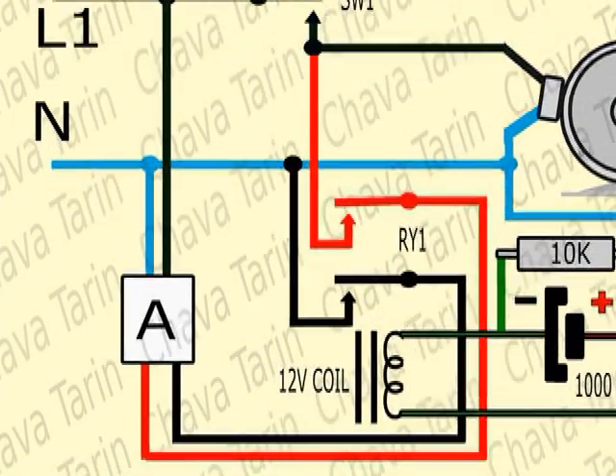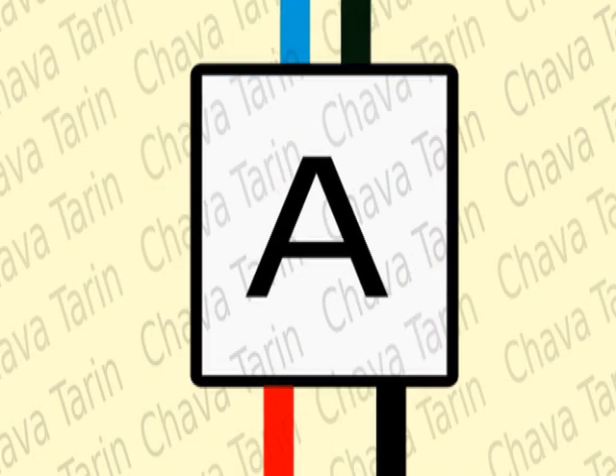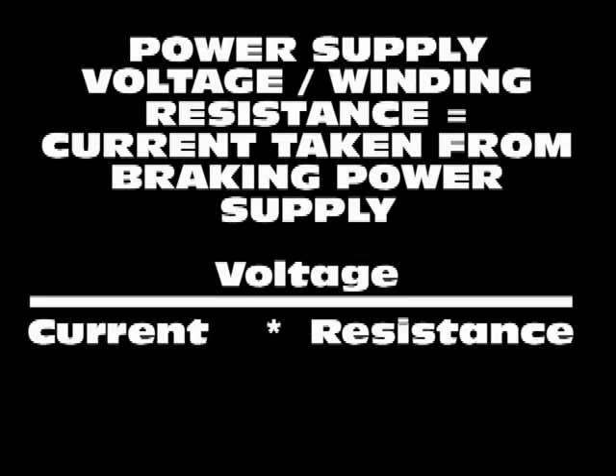Another important factor is the voltage and current capacity of the braking power supply labeled A. You want to measure the motor winding resistance by using an ohmmeter while the motor is disconnected from the power line.